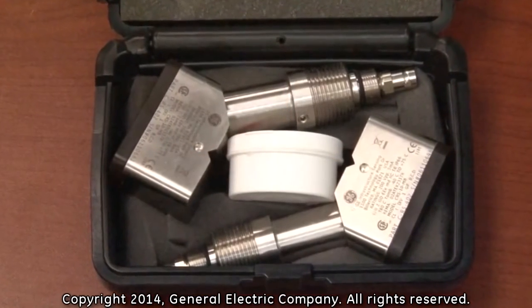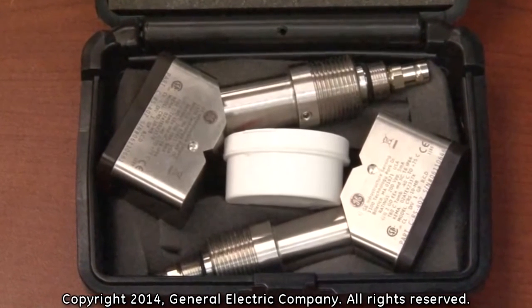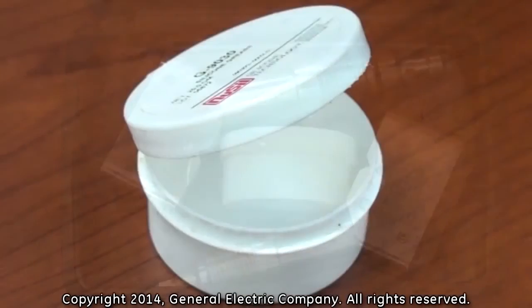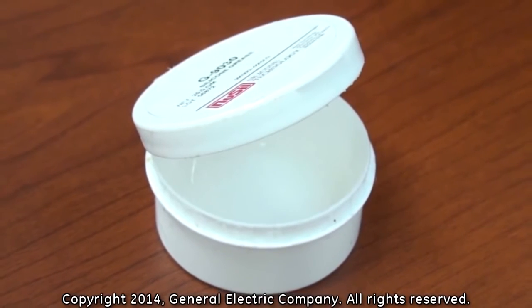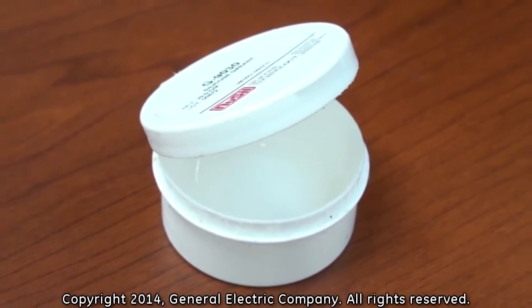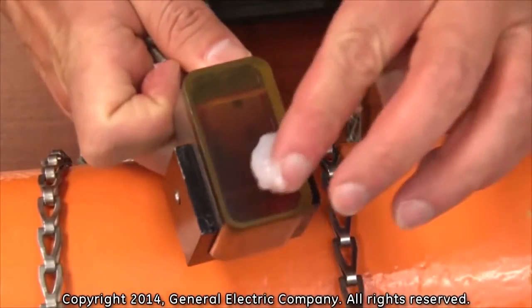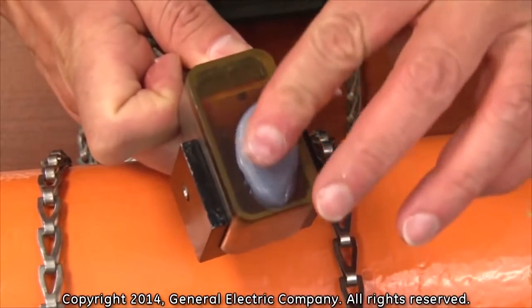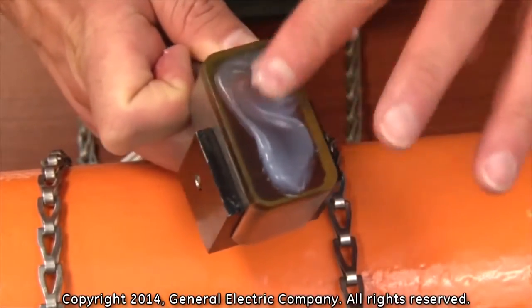Before installing the transducers, you must apply couplant onto the face of each transducer. Use only the recommended couplant for your specific transducers and application. Use as much couplant as you would toothpaste on a toothbrush, and evenly cover the face of the transducer.